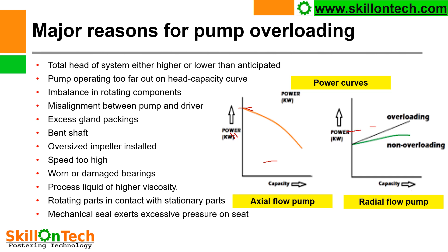If your pump is running on the HQ curve at BEP (best efficiency point), then it will take minimum power. But if the pump is running out of BEP, then the pump will take more current, and that will be a condition of overloading, as you can see here.